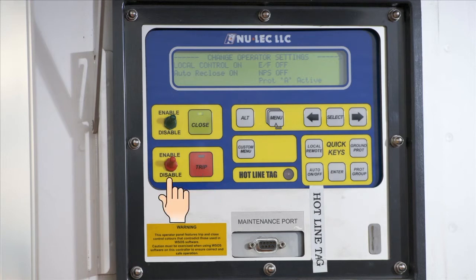Trip disable switch disables all trip operations. When the switch is in the disable position, the trip circuit in the switchgear is electrically disconnected from the control electronics. Thus, the switch provides a physical isolation point for the control circuitry. The switchgear cannot be opened, an audible alarm in the panel will sound, and the disabled LED in the trip key will flash. The trip key operates normally when the switch is in the enable position. This switch also prevents a close operation, so that the switchgear cannot be carrying load without the ability to trip.